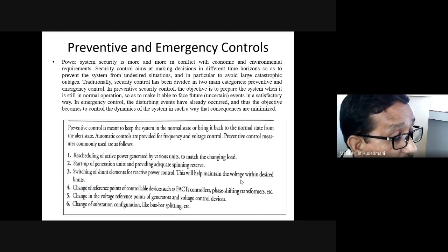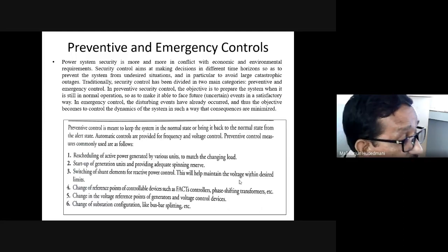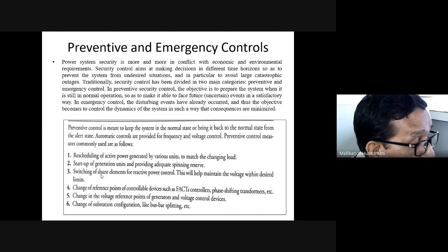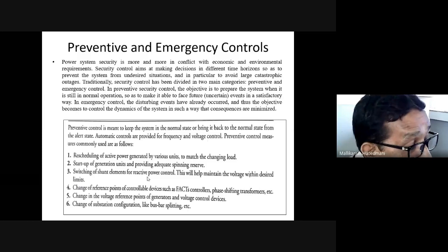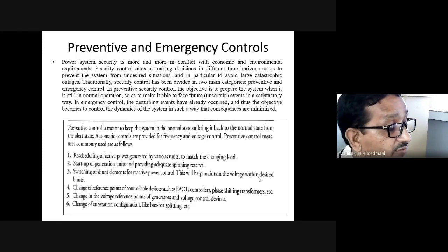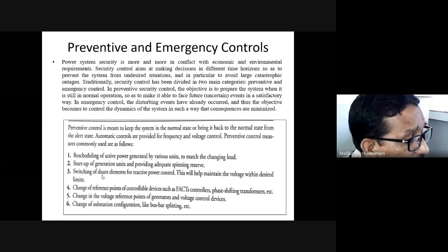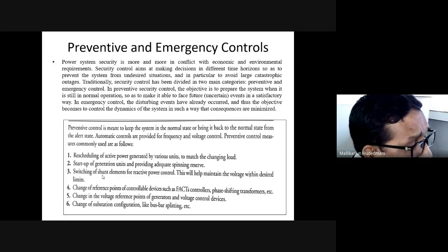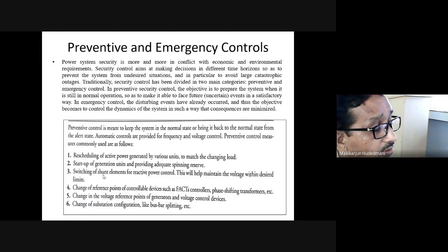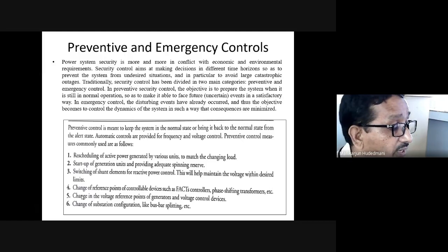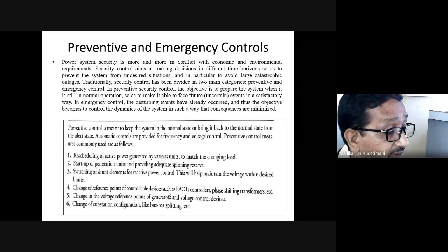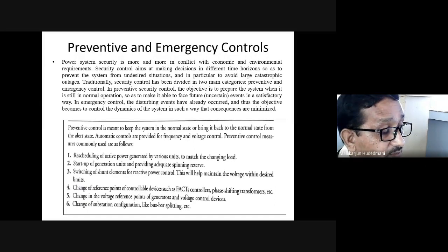Hence, if the voltage which you are not able to maintain well within the specified range, we have to identify the root cause for that. What is the compensating point where, if I apply the compensator or switching elements like a compensator, capacitive element, inductive element as required, which will definitely shift the working voltage difference. This is a preventive control, which you are able to manage before really it demands you. Hence, it must be planned properly.